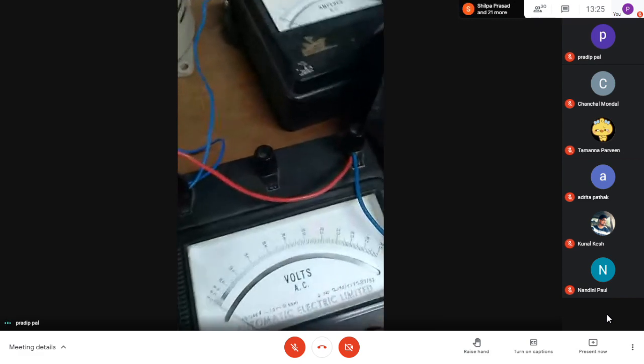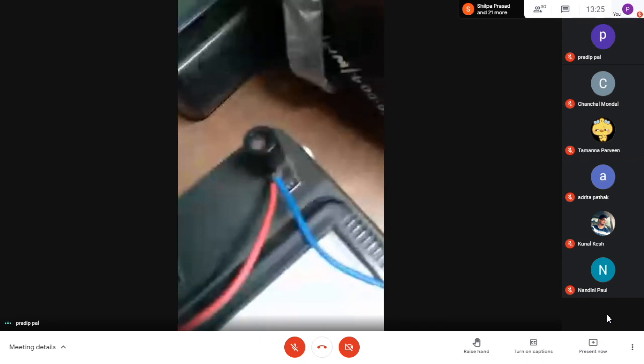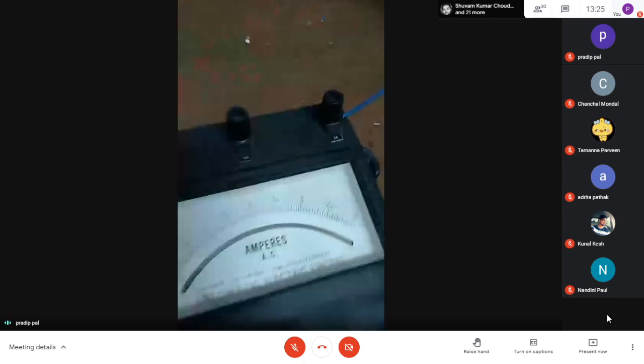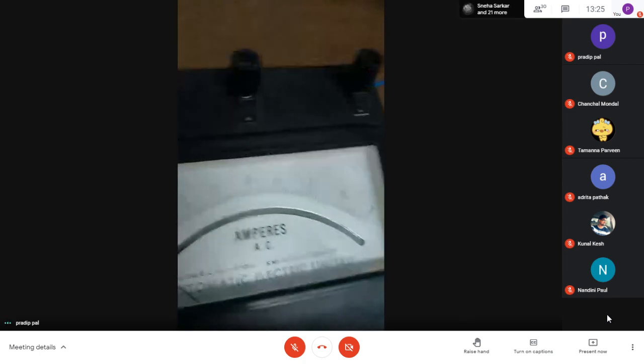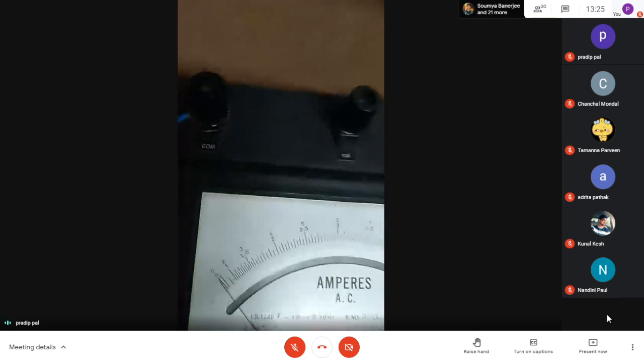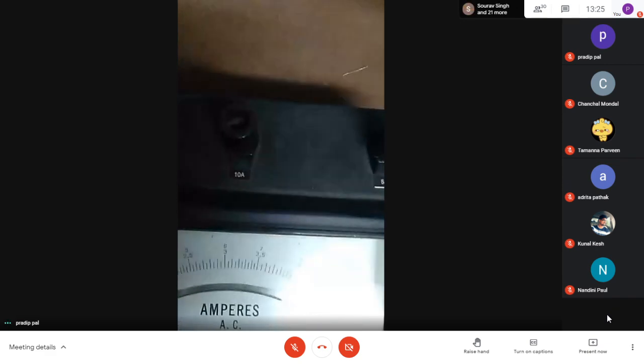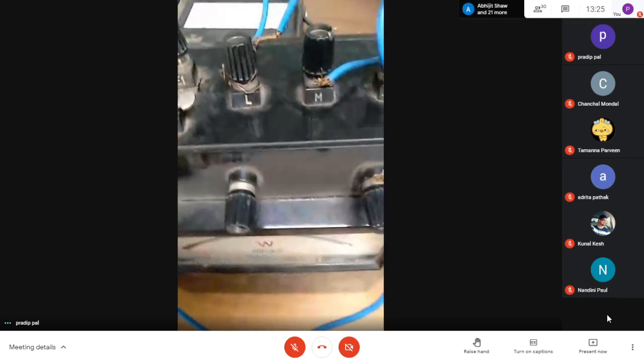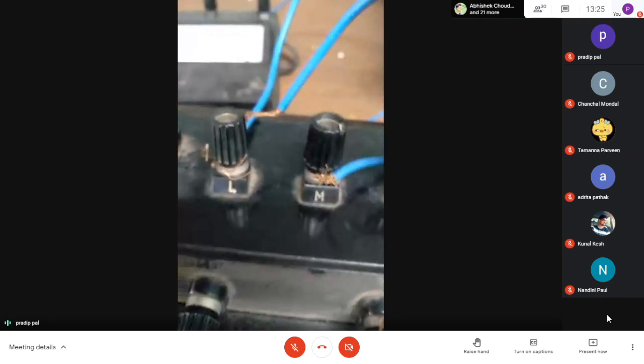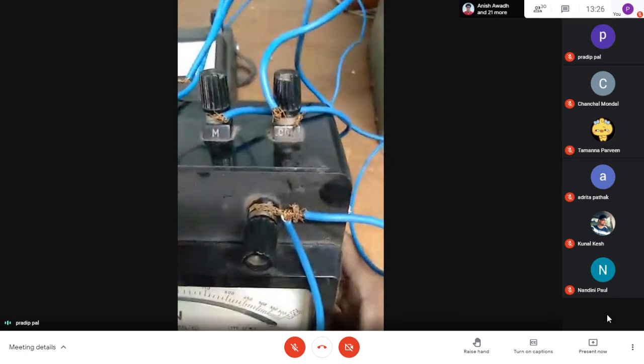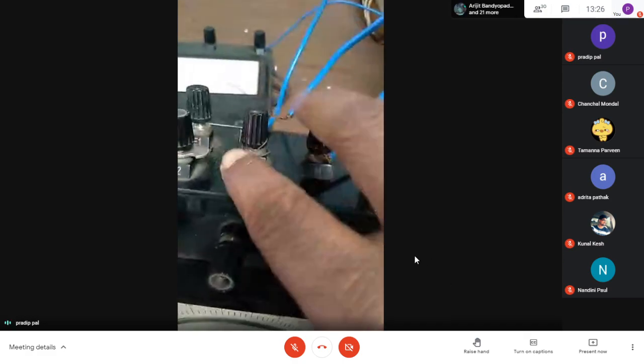This ammeter has three terminals, but we use two of them - the common and either 5 ampere or 10 ampere. This one is a wattmeter with four terminals: M, L, C, and V. M and L are internally connected by a current coil, and C and V are internally connected by a pressure coil. In this instrument M and C are open, so we short M and C.